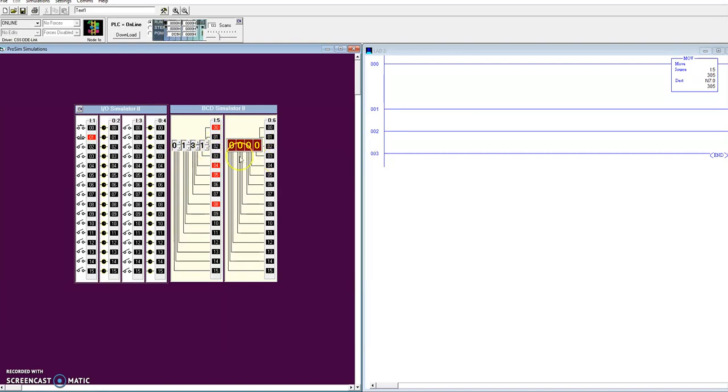The problem is, because this data entry thumb wheel device is wired up in BCD format, if I just take the value of that register, it doesn't show me 131, it shows me 305, because 305 is the binary representation of these 16 bits together.